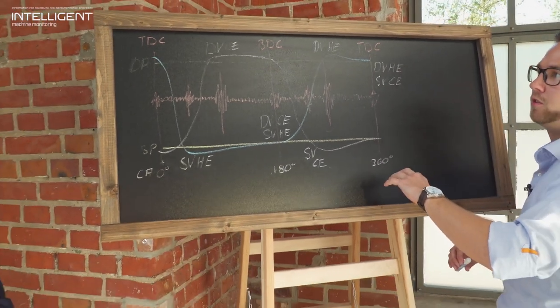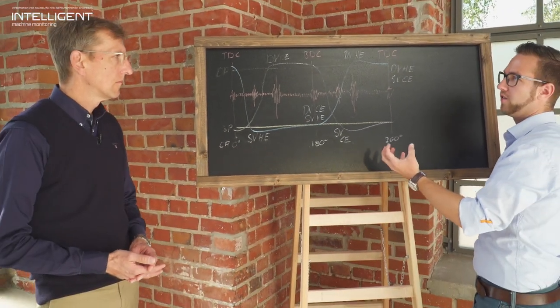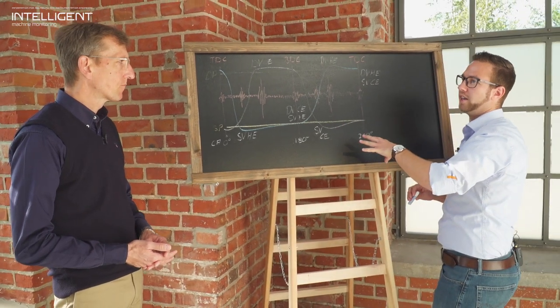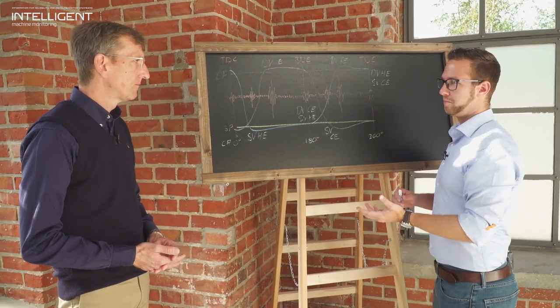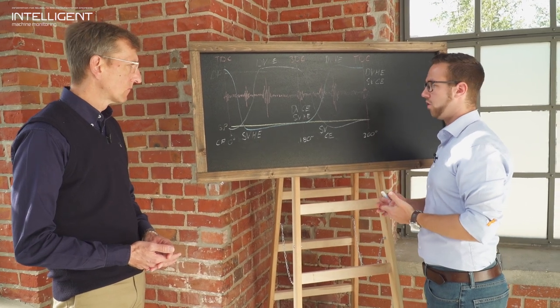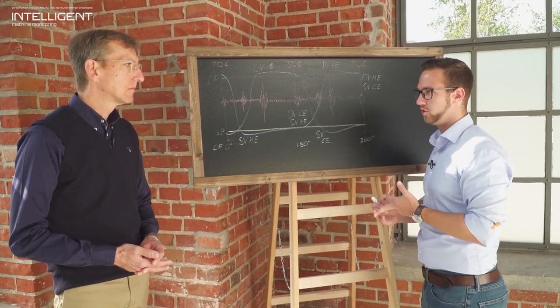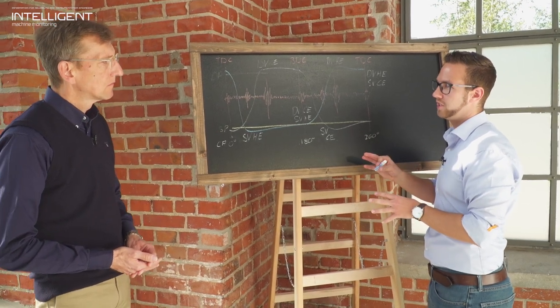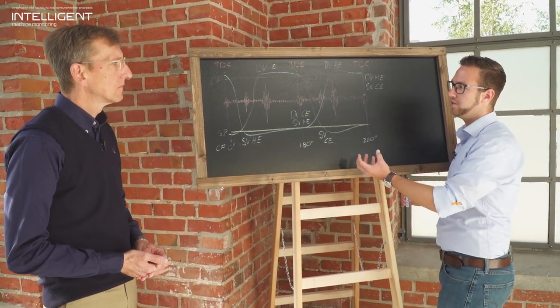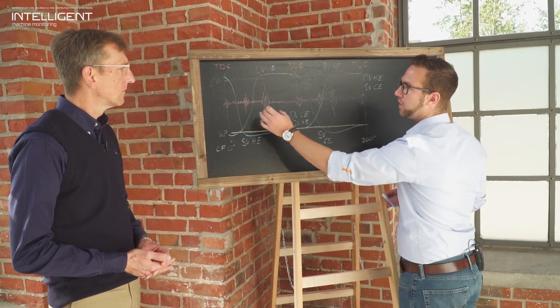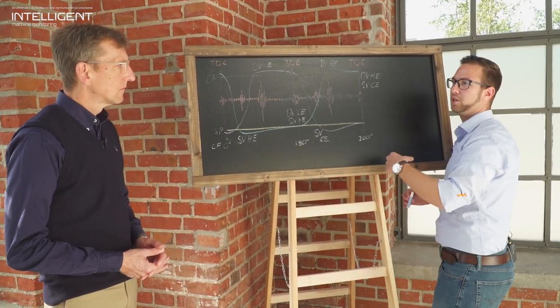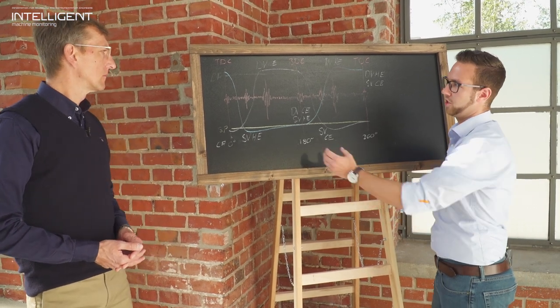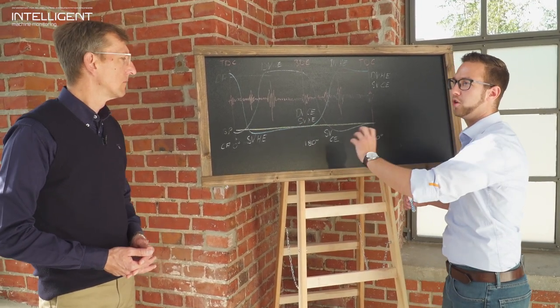That is how we monitor the different valves because we know where every valve is opening, which is hard to do if you don't know exactly where your valve is opening. If you start to play around with your process, maybe by active valve control or by bypasses on your compressor, these points of time will shift with your change in pressure and process, and then it's very hard to monitor those. Those peaks won't be at the same point of time anymore.